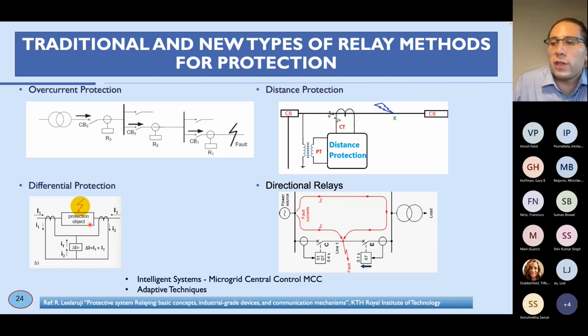Then we have the differential protection, where basically we measure two different ends of the line. By measuring two different ends of the line, we know by basic Kirchhoff's law that the current that comes in is the current that comes out if we consider it as a big node. So from this definition, we can identify if there is a fault, because the current coming in is not the same as the current coming out, theoretically. So we can compare in a line, which we call the protection object, which can be a distribution line, a transformer, literally anything between the boundary, and we can measure and protect it if there is a ground fault or basically any type of fault. Here I'm showing a little bit of the algorithm, the diagram.